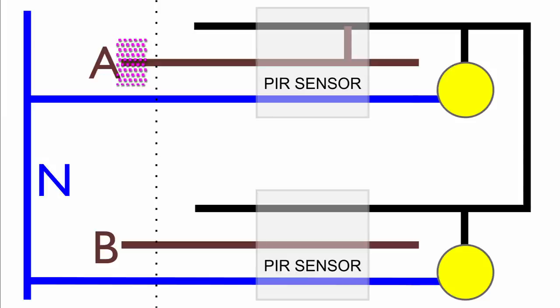But crucially when power is applied to A and B is disconnected we don't get any voltage showing on B at the consumer unit because of course all the sensors on circuit B are switched off and there's no connection between the switch line and the line B there. However if we remove power to circuit A, that link on A and that faulty sensor is still there. Now if we turn power onto circuit B, we just get the lights turning on because when these sensors are first powered up they actually connect through on the relay for a short period and then they go off after the defined time. So what we actually get then is that we've got power coming on B, sensors are switched on so it connects through to the switch line, and even though there's no power being applied to A from the consumer unit, because there's that stuck relay in one of the sensors, we also get power coming back on A, and of course all the lights are turning on because of the link on the black wire. So that is how we're getting a situation with B on, we're getting power coming back on A, but if we put power on A only we don't get anything coming back on B.